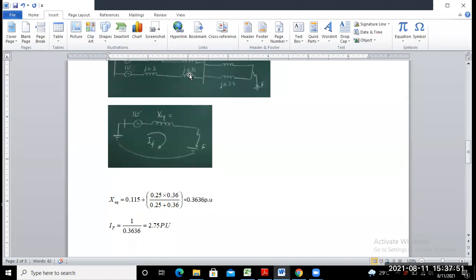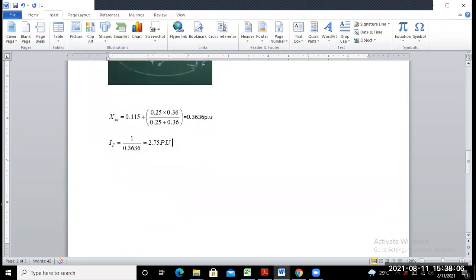Or maybe the per unit value of reactance of the transformer from either side is the same already. That means low voltage side or high voltage side. We already proved it in the previous classes also. So just multiply this per unit value by the base value, is it not? Then you will get the value of fault current in actual value, in unit of ampere.